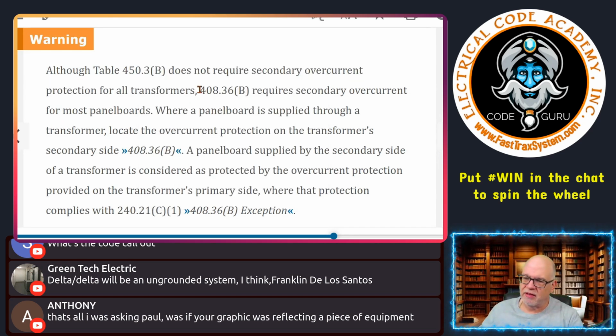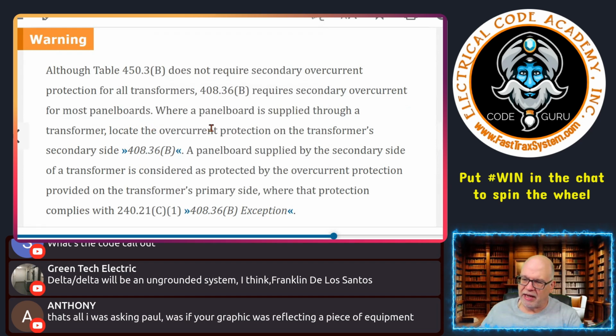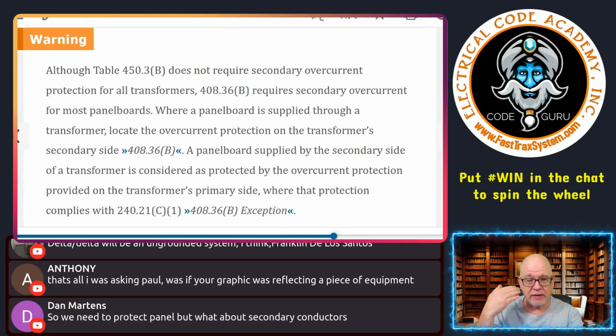then 408.36(B) requires secondary overcurrent protection for most panelboards. So where a panelboard is supplied through a transformer, this is our typical application. I put the transformer in, I have primary protection of that transformer, and it goes through the transformer. I have secondary conductors, and now I'm feeding a panelboard on the secondary side, which is probably what you do most of the time. In that scenario, I also have to protect the panelboard. So indirectly, I need to put a breaker or fuses in there to protect the panelboard. So in that scenario, it requires secondary overcurrent protection for those panelboards.